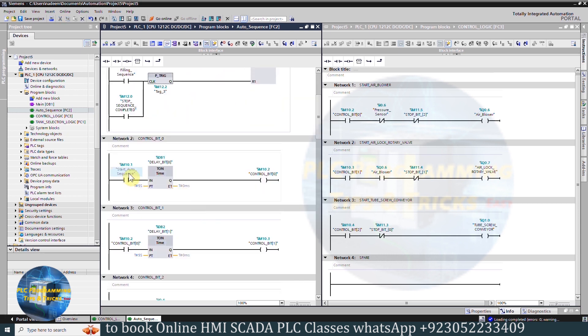In Network 2, if the start auto-sequence bit is on, it will start a 5-second timer. Once this timer is over, it will turn on control bit 0. This control bit 0 is used in the control logic function — as bit 0 turns on and the pressure in the line is okay, it will turn on the blower Q0.6.